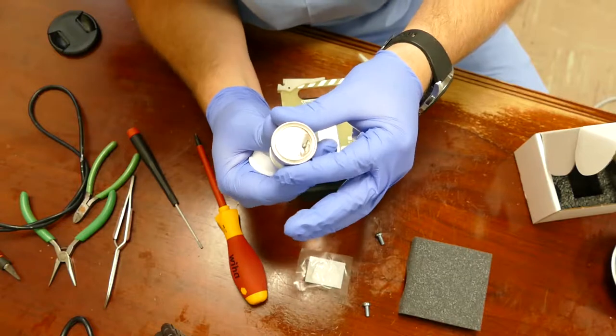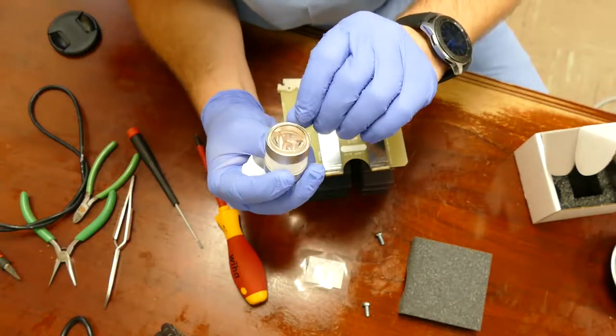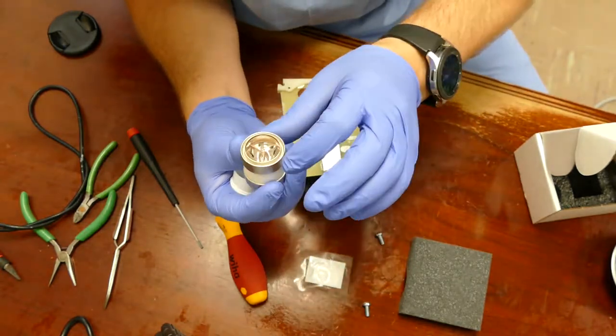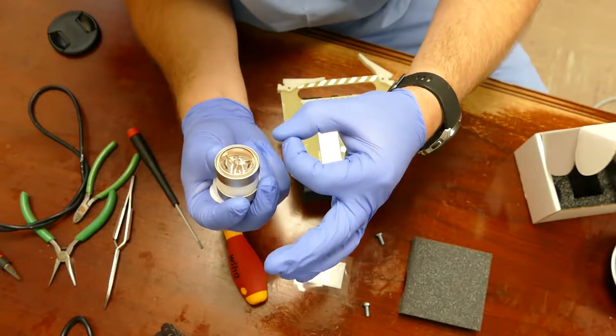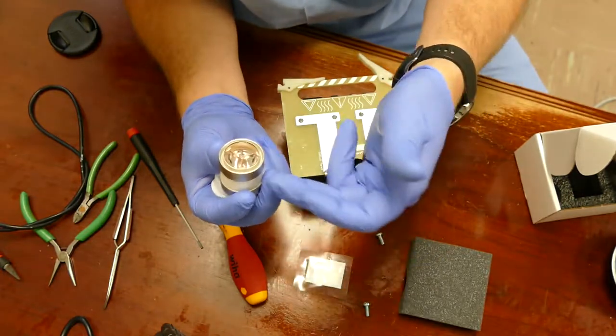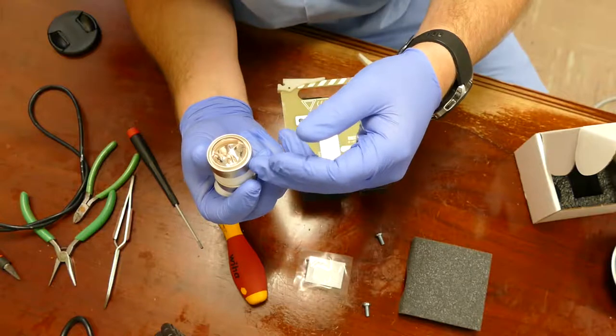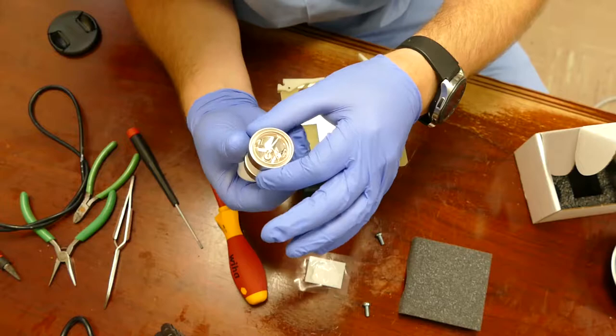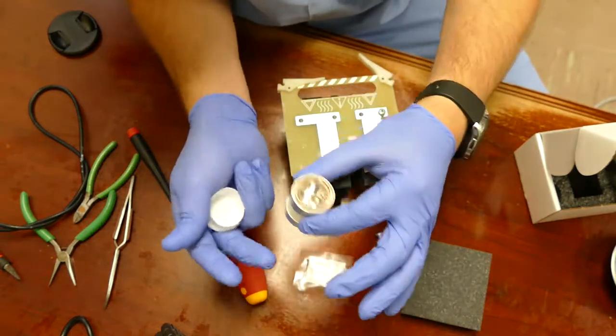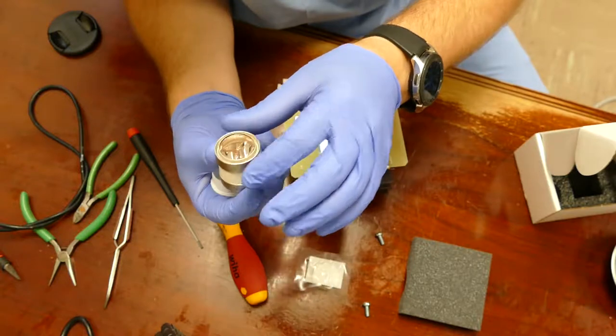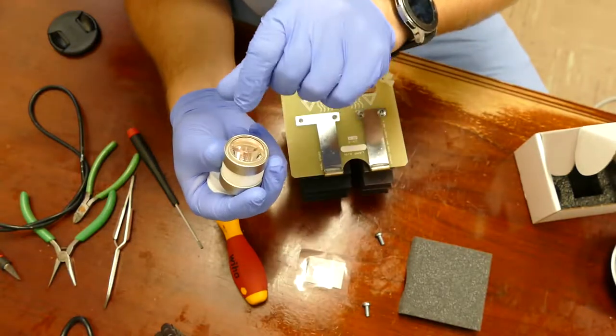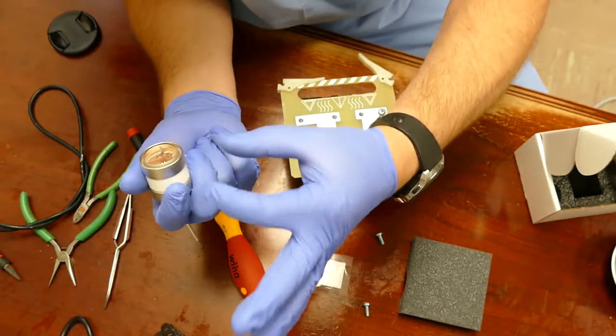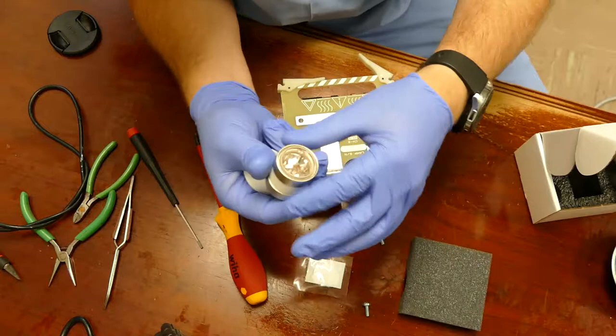There is no visible spot on a new bulb, barely any, and that's just from testing. But on an expired bulb, as you'll see on this guy, there will be a sun spot or a burn spot, and sometimes even browning on the reflector. And the browning is where the arc is starting to arc over inside the lamp, and that's very bad. It'll basically cause the bulb to eventually self-destruct. So on a bulb, if you're looking to see if it's new or not, just take a look down at where the anode and cathode gap is, and you'll see a large black spot, and that means that it's a spent bulb.